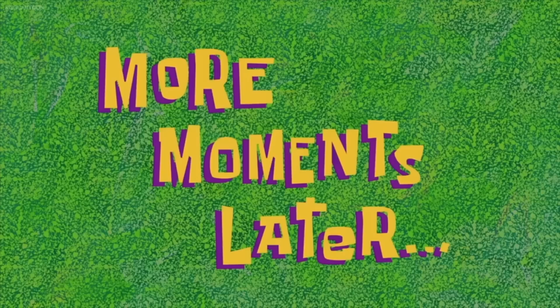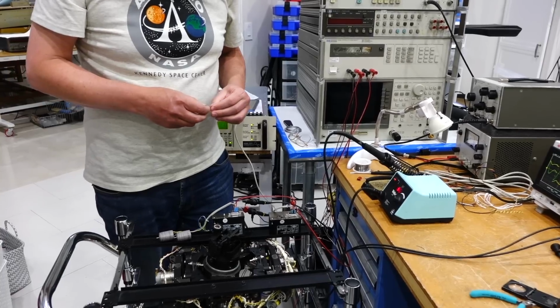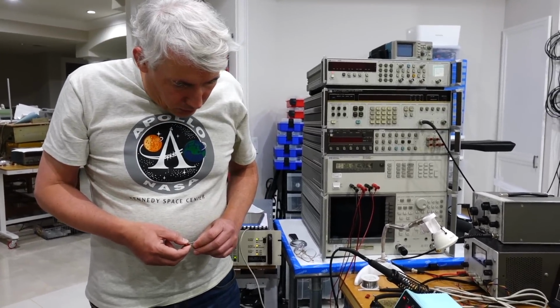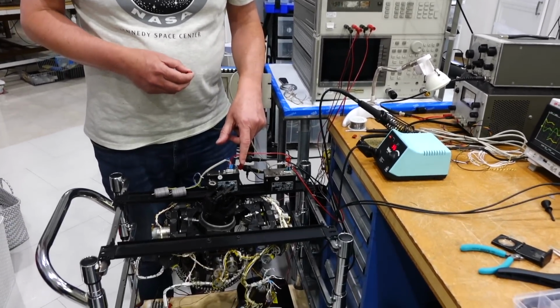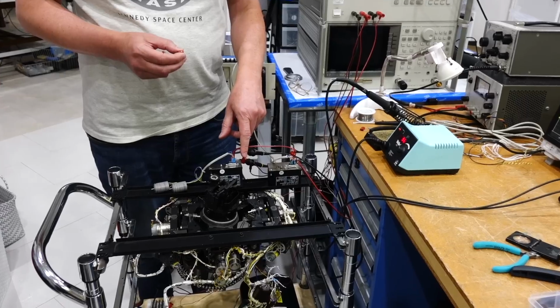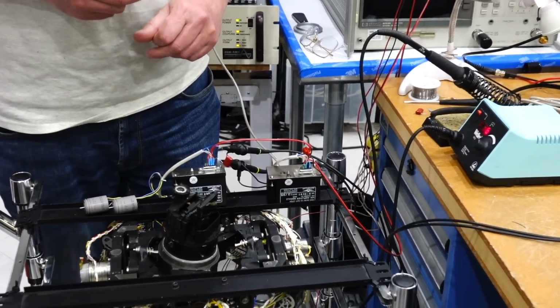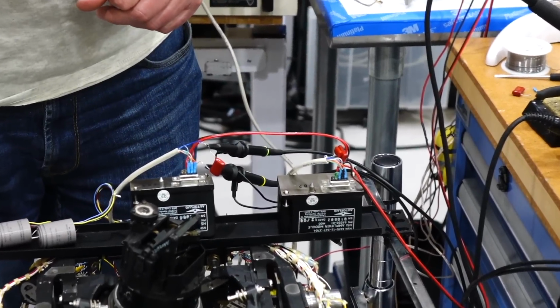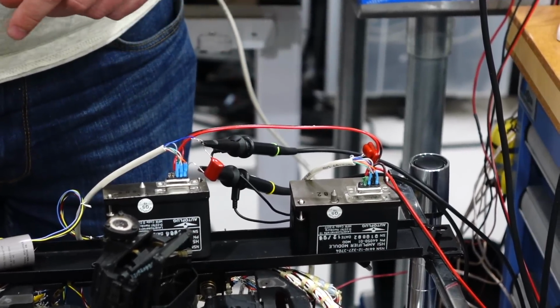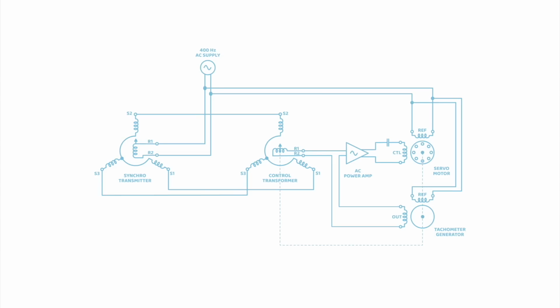More moments later: You found the issue? Yes, the issue was the dephasing capacitor, which is necessary for an AC motor. You need 90 degrees between the control and the reference coil. It's done with a series capacitor. Ah, the dephasing capacitor. We hadn't talked about that one and left it as a mystery on the schematics until it decided to bite us in the butt.